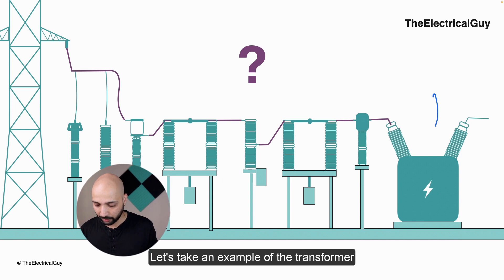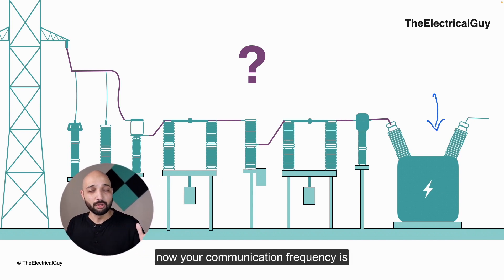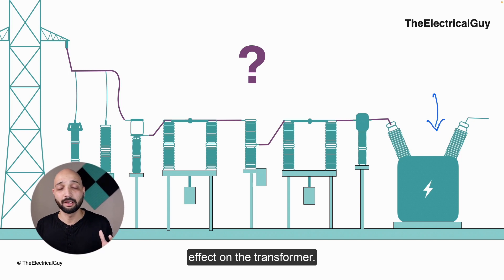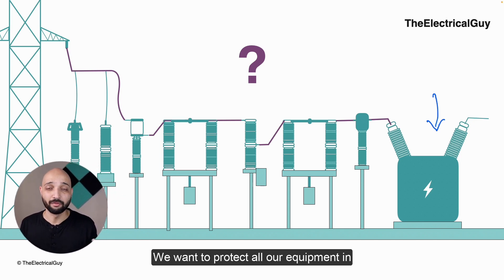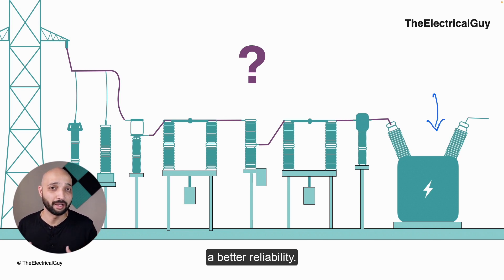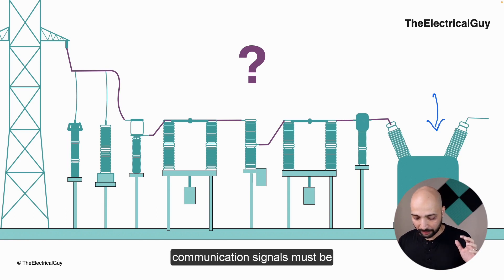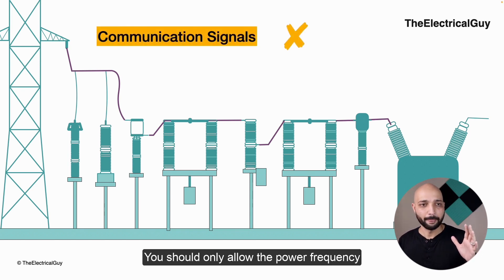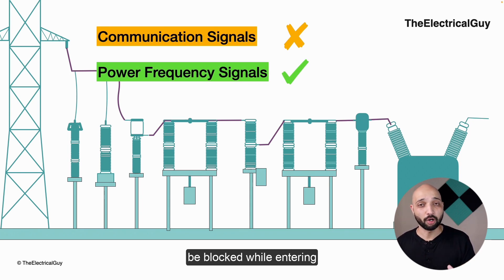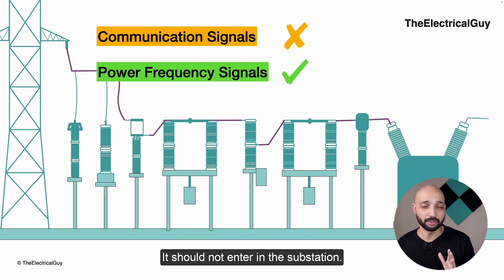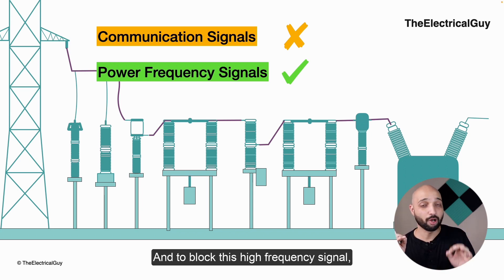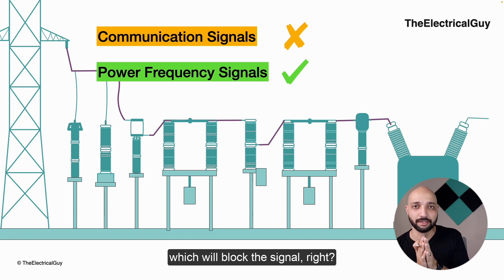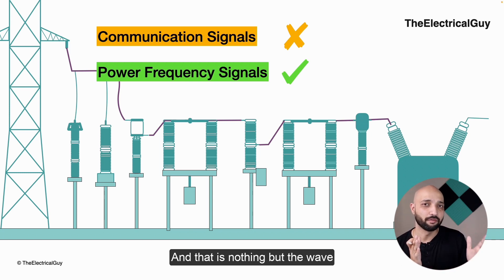This will definitely have some adverse effect. For example, if your transformer is designed for 50 hertz and the communication frequency entering is 200 kilohertz, it will have an adverse effect on the transformer. We want to protect all equipment in the substation for better reliability, and that is why communication signals must be blocked at any cost. Only power frequency signals should be allowed; communication signals must be blocked from entering the substation.